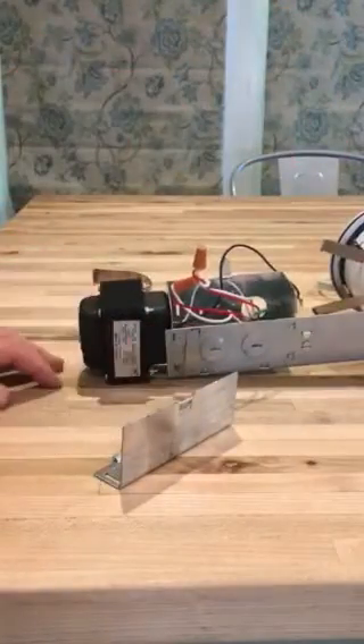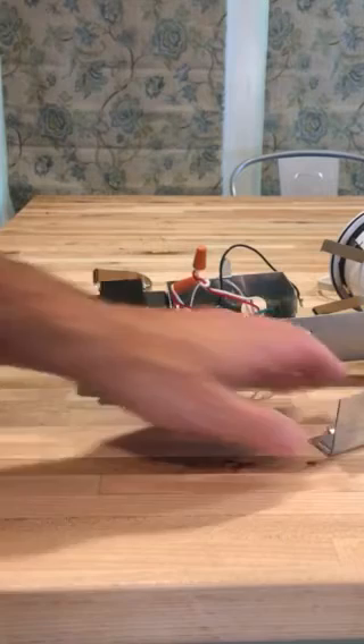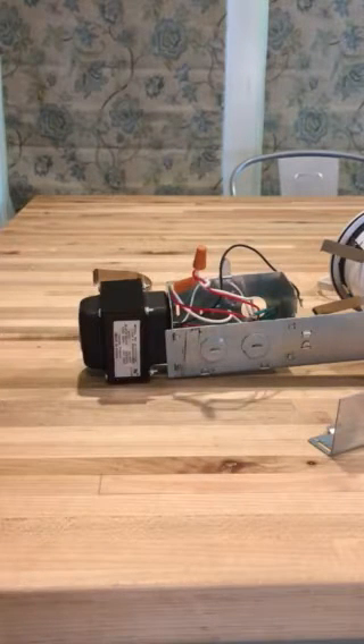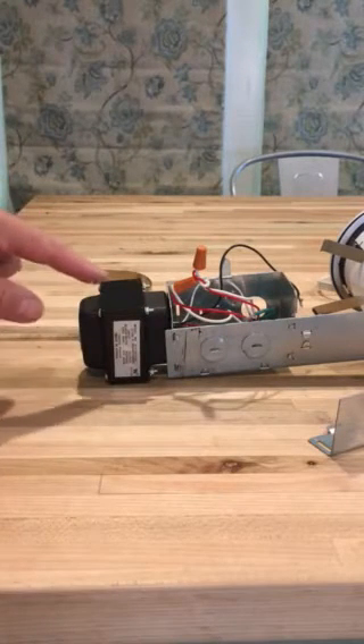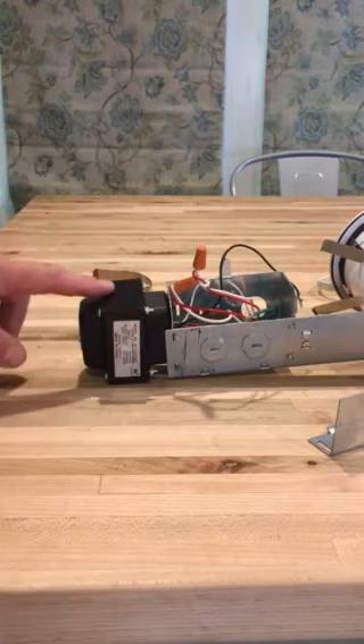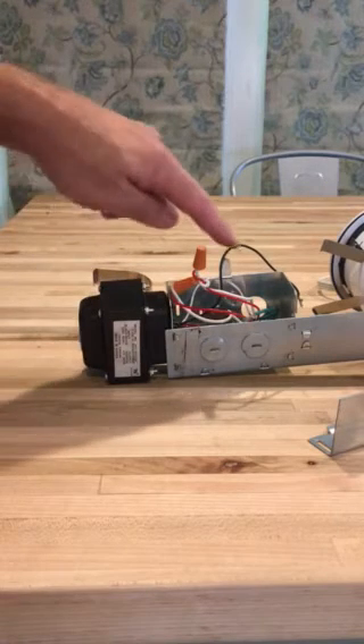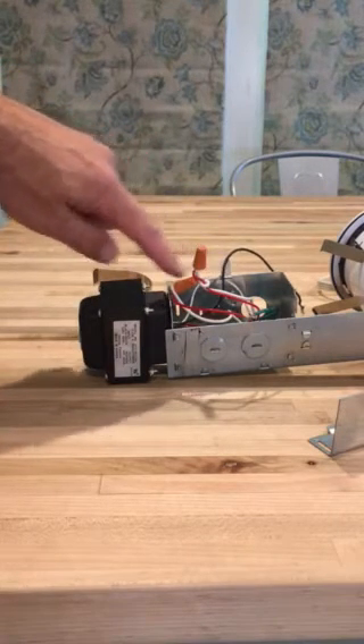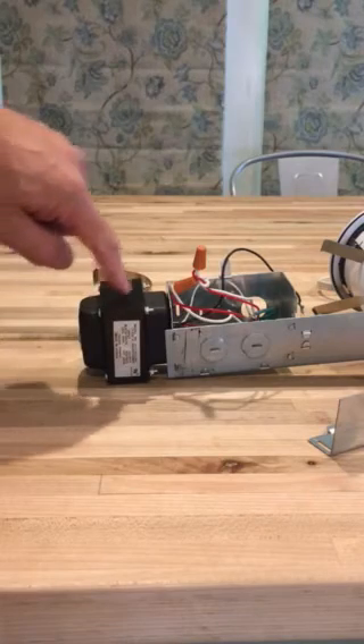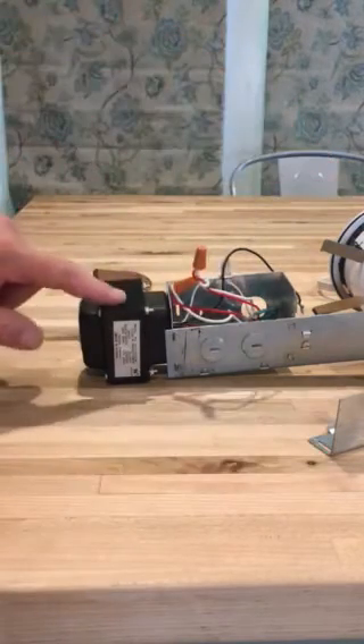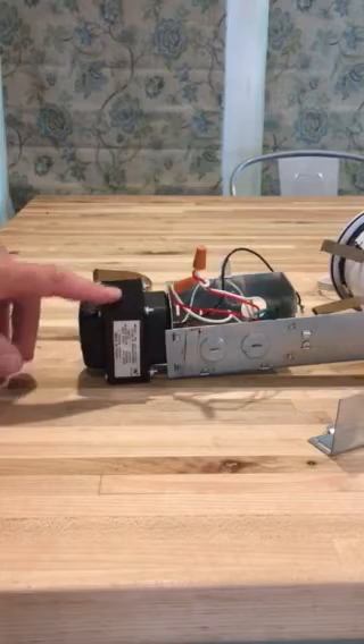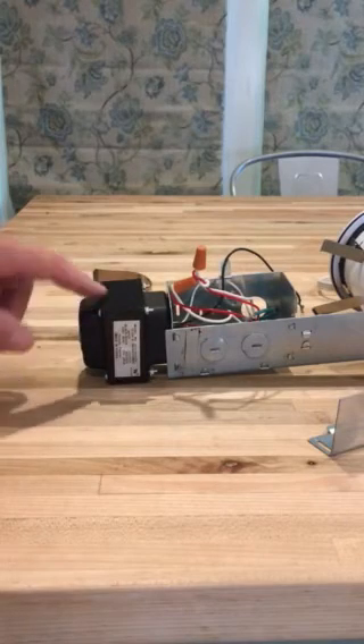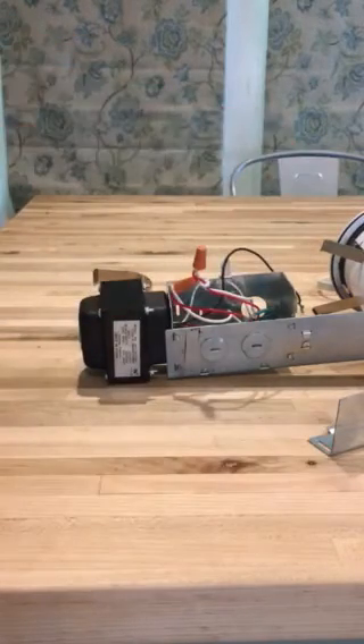So if we were going to dim this, we'd say it calls for a magnetic low voltage dimmer. We would actually be using a triac dimmer to dim the line voltage into the transformer and then back out to the light. So we're actually dimming the line voltage to the magnetic transformer, which turns it to low voltage and puts the light out.